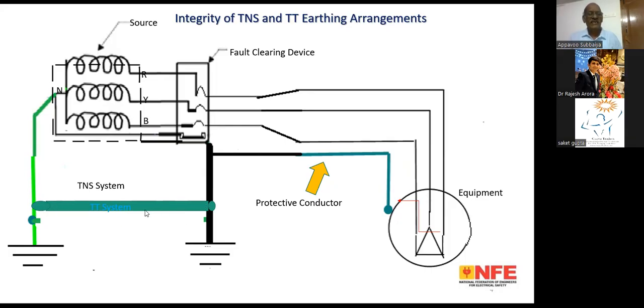These are rigid flats. PE conductors are rigid flats according to the point of application. They will be rated for the fault level, so naturally they will be of higher size, and the ohmic value will be in the order of milliohms. But there will also be a possibility of another earth return path through the general mass of earth to the source. But it will be negligible, because this circuit will be in the order of milliohms, whereas this circuit will be more than 5 to 10 ohms, depending upon the site condition and soil resistivity. So that is 10 to the power minus 3. So only a 1,000th part will be flowing through this circuit.